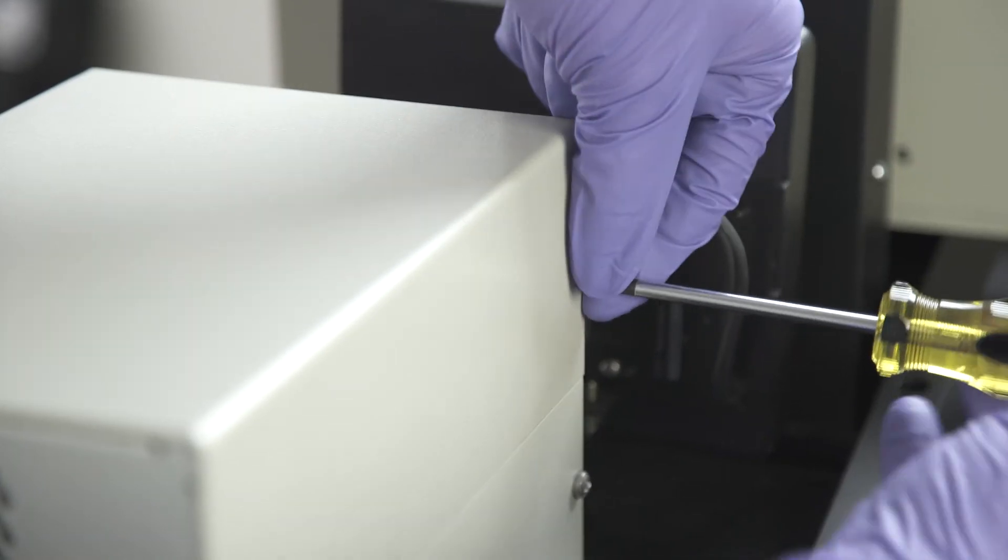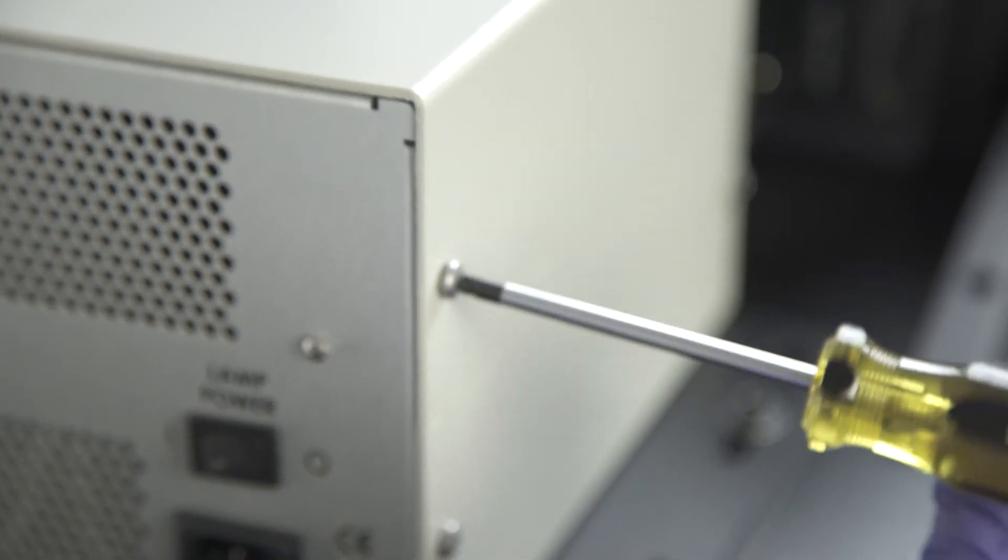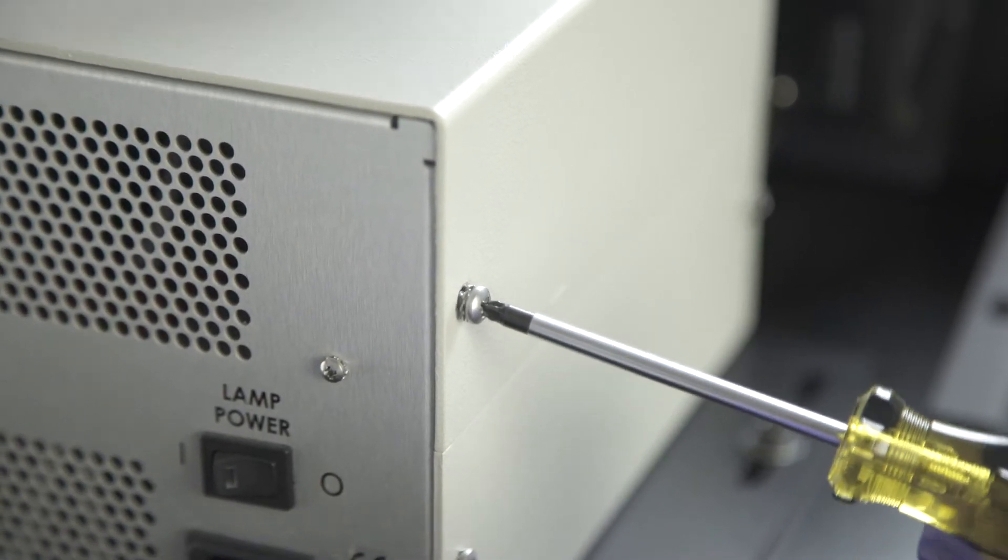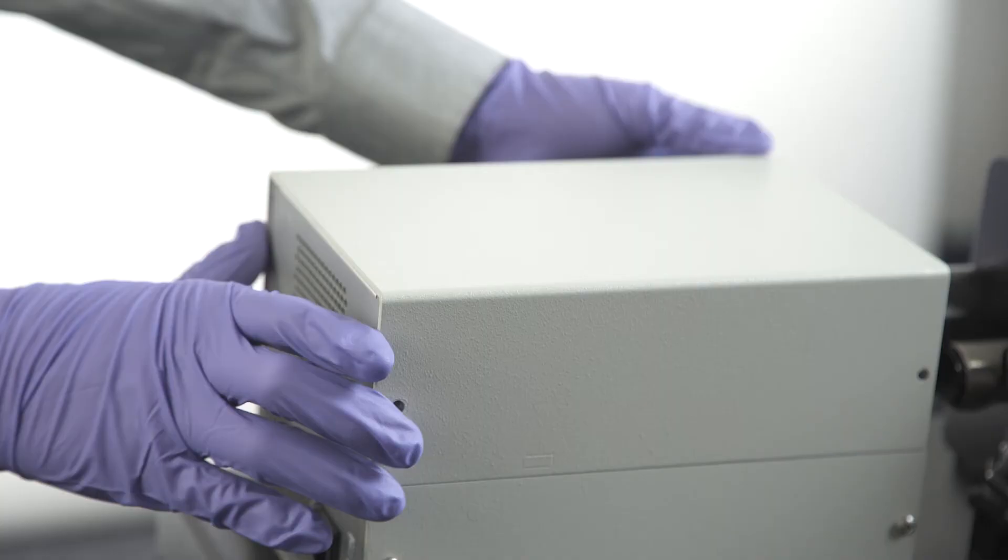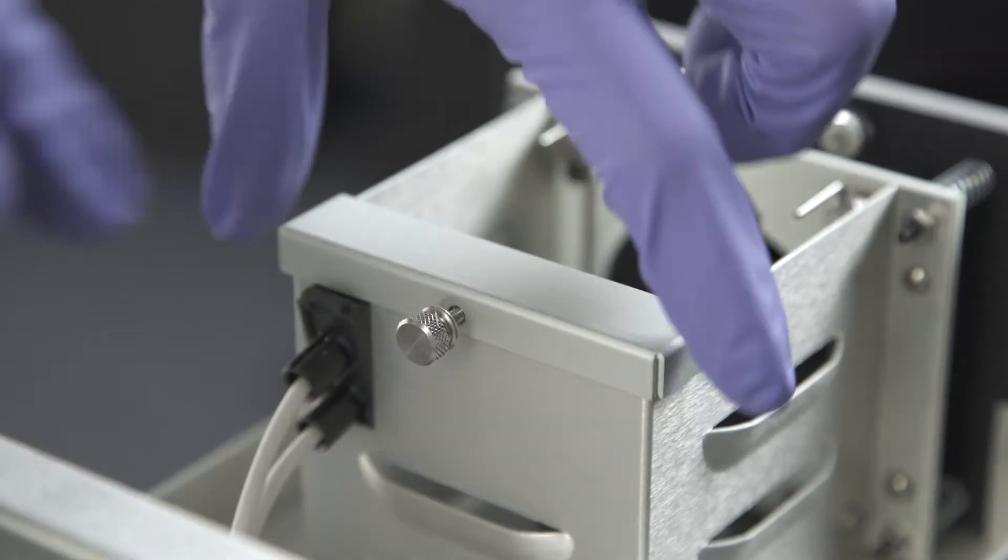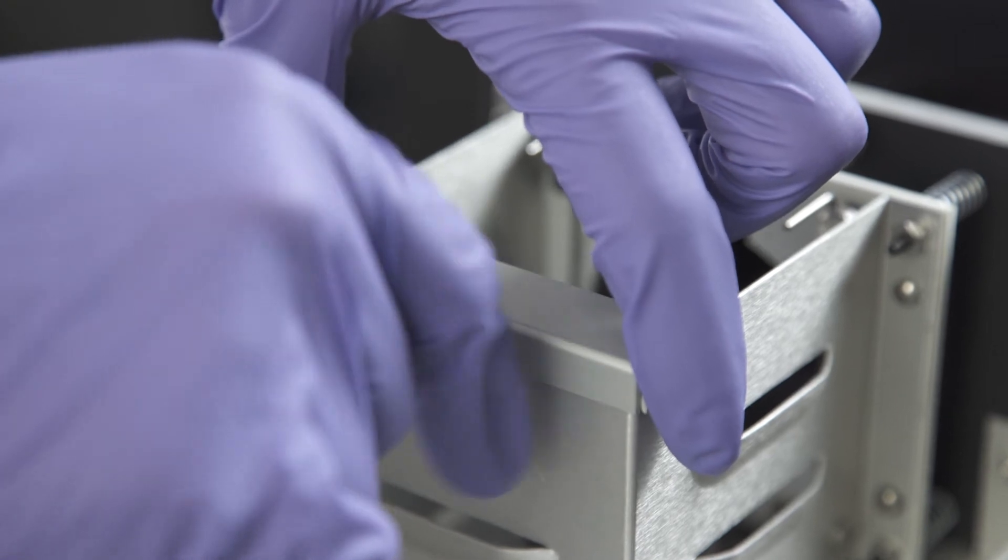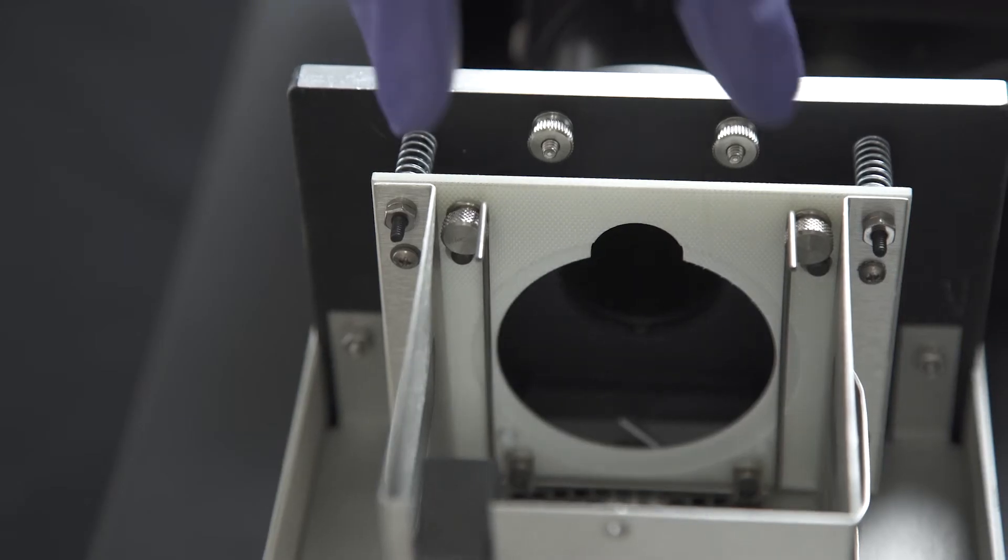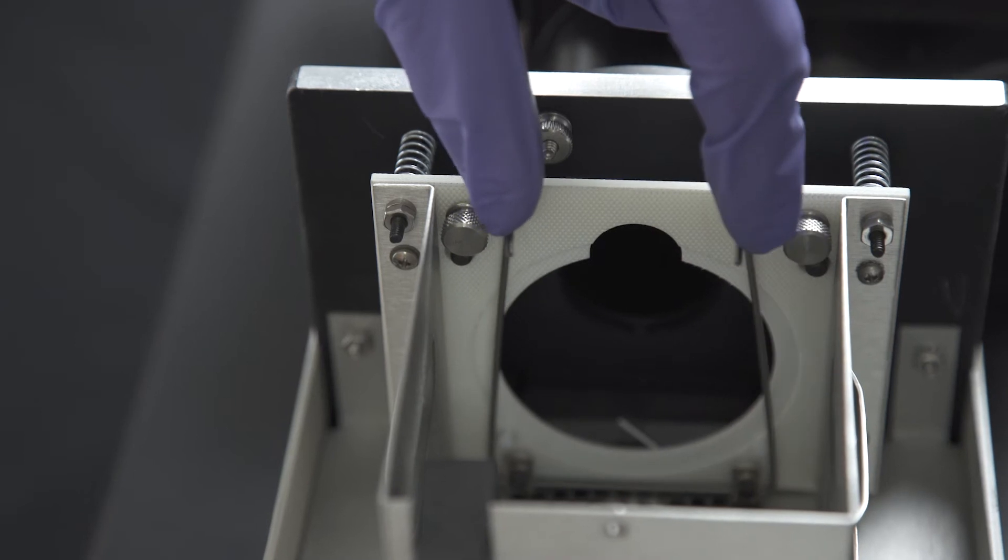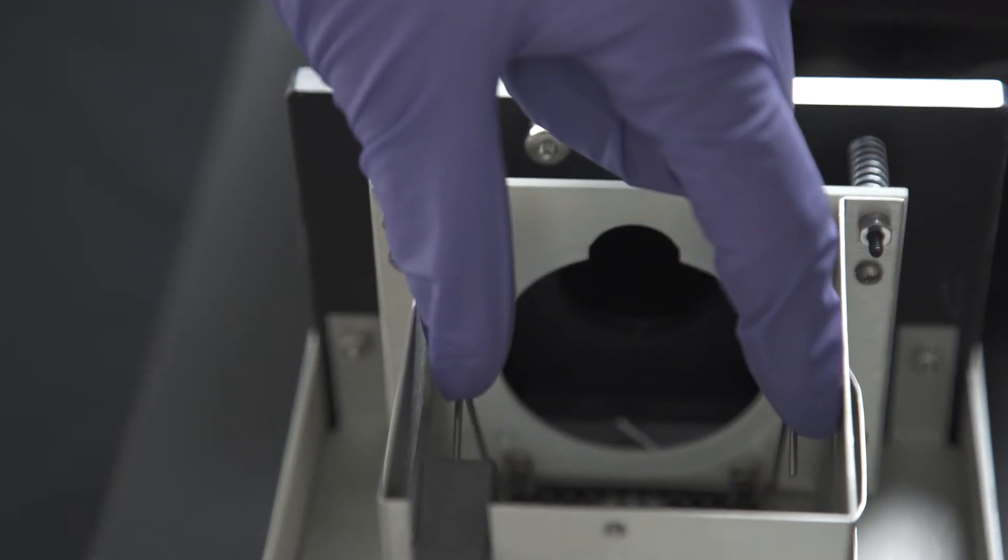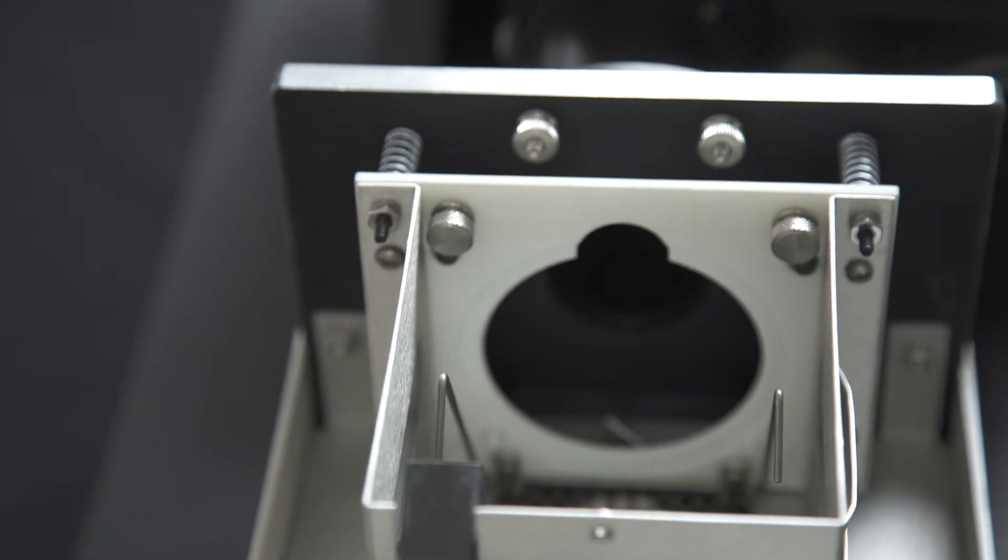Next, we install the 100-watt Xenon Arc Lamp into the lamp housing. Using a Phillips screwdriver, remove the four screws of the top cover to take off the lamp housing cover. The lamp cage retention cover is removed by unscrewing the thumb nut. Gently squeeze together the handles of the lamp retaining clip to disengage from the posts, letting it pivot back to its open position.